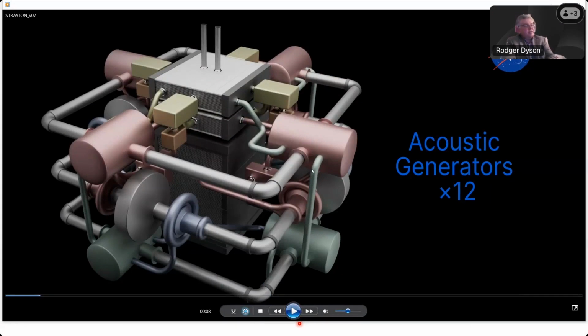The turbo machinery is in this middle quad, and there are 4 of them, connected together. So it ends up having a 4-stage compressor and a 4-stage turbine expansion. It turns out with closed cycles, that's the knee in the curve for efficiency, 4 stages for compression and 4 for expansion. So the Brayton part of the cycle naturally wants to be arranged in groups of 4 like this.